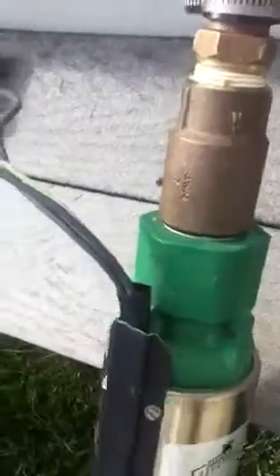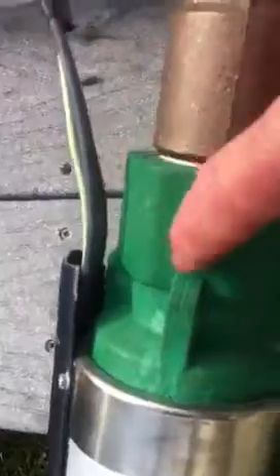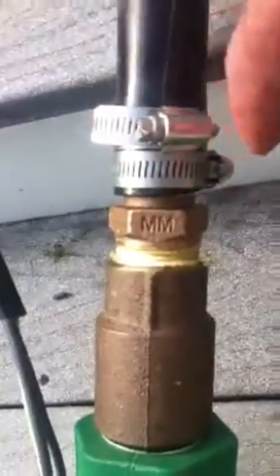You can see on this pump, the pump leads coming off of the pump. This one has this really nice little grommet that slides up in there and protects the wire. This is one of the points of concern for me, where the wire comes in contact with, in this case, this is not a metal housing on this, but this is metal. Of course, these clamps are metal.